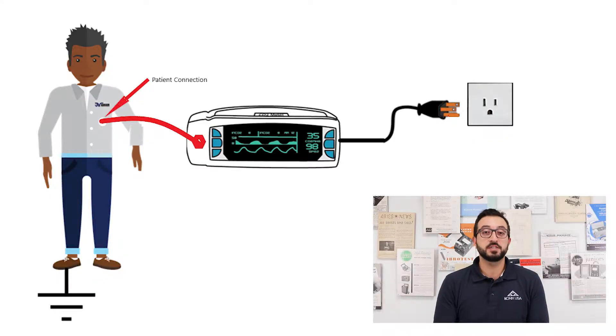In order to understand the patient leakage test, it's first important to know what are patient connections and how are they defined in the IEC 60601-1 medical device standard. Per the standard, patient connections are defined as any points of a medical device that make contact or come in contact with the patient.